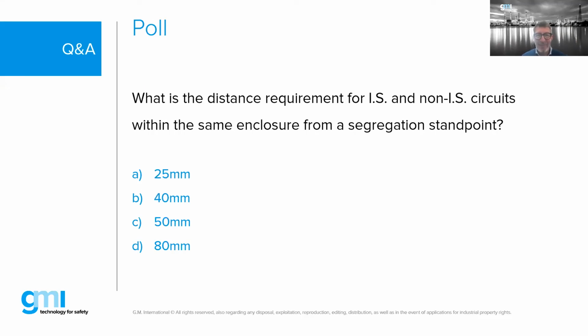So, this segregation, for example, there's a limit on the size of a barrier we can design, because we have to keep the segregation between the input and the output wiring, between the two sides, the IS and non-IS side. And that's why you cannot go smaller than this distance. So far you have all answered correctly.